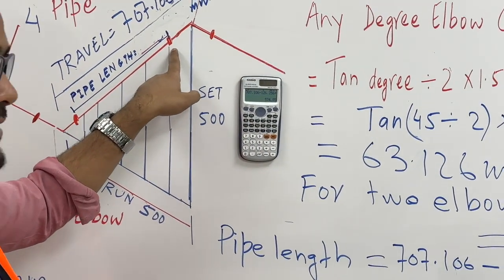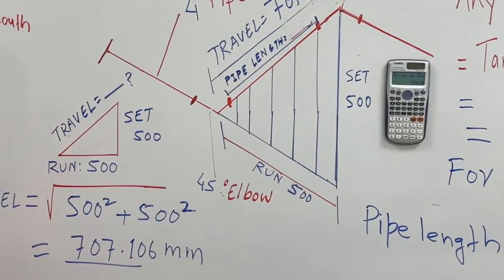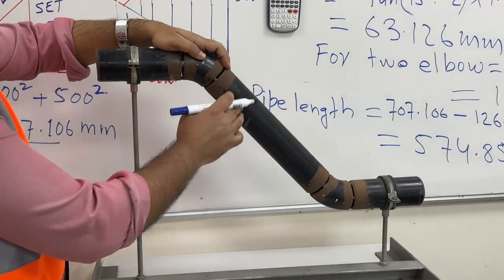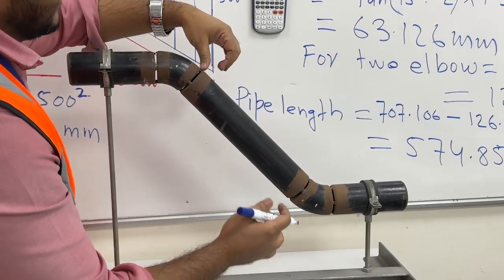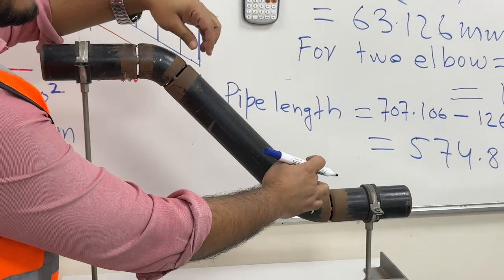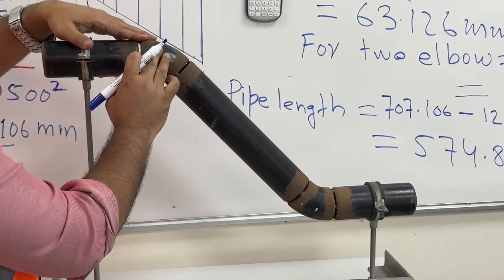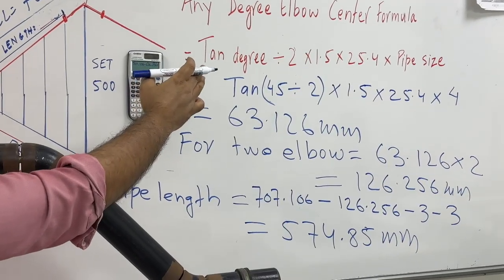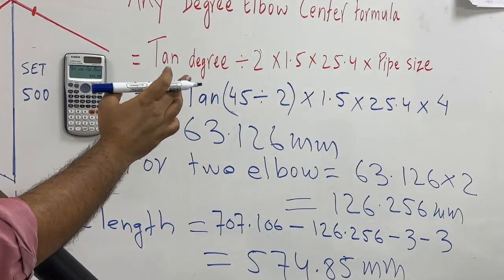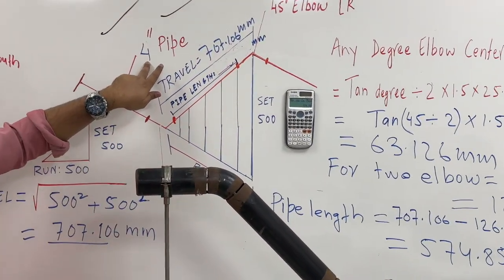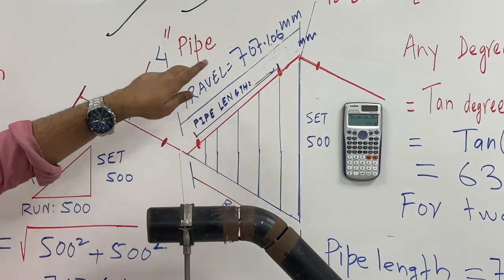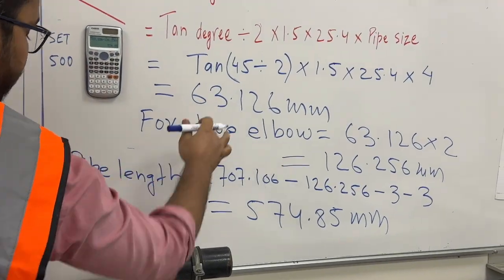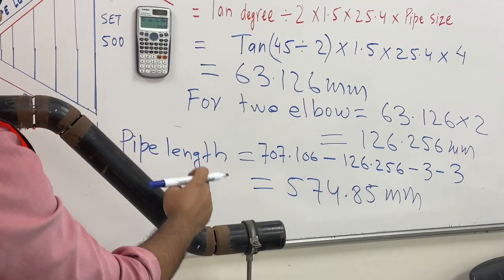This is the pipeline from here to here. Now to understand: here is our elbow and here is our elbow. To calculate the pipeline between them, we calculate the elbow center using the formula: 45 degrees divided by 2, times 1.5, times 25.4, times pipe size. Pipe size is 4 inch, so we keep pipe size as 4 inch. This gives the measurement for one elbow center. For the second elbow we multiply by 2.